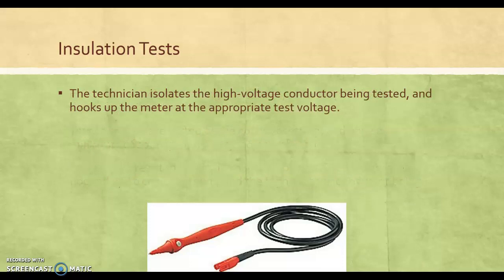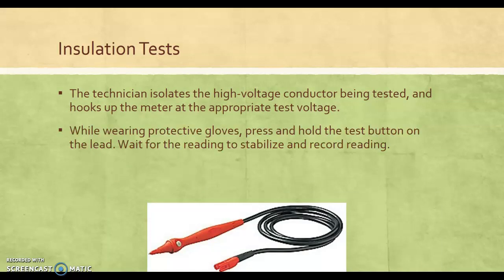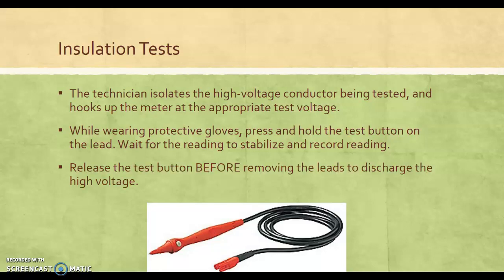So make sure you isolate what you're testing, just like an ohm meter. Nothing there has changed. They recommend to wear protective gloves, but again, that's up to you. Make sure you're not touching anything that you're testing, and not leaning up against it, influencing that. Or if you have a pacemaker, you're vulnerable. Again, I know I should say always wear gloves when doing this, but moving on. Always wear gloves when doing this.